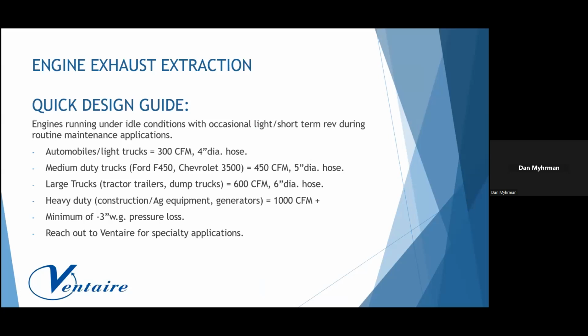We actually do have an exhaust output calculator that we can input all this information on and come up with the approximate output of the engine. In our systems, one of the issues we do see oftentimes is the static pressure is kind of an oversight, and oftentimes you just kind of throw random numbers in there. I wouldn't recommend anything less than 3 inches. With our system, static pressure is never consistent because the hoses are always reaching various locations, exhaust pipes. Sometimes you have a spaghetti of the hose just to reach some exhaust pipes. So static pressure is never constant with our systems.